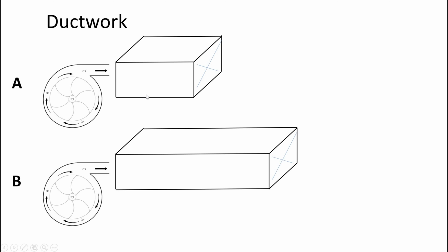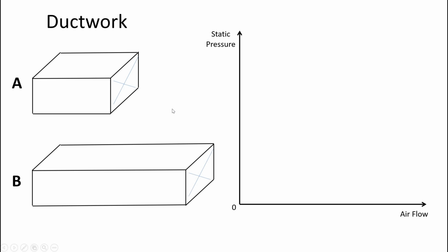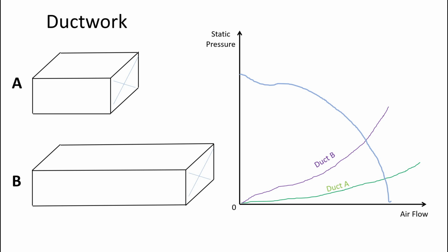The fan needs to create less static pressure to push air through ductwork A than through ductwork B. Let's illustrate it on the chart again. Low static ductwork A would look like this on the chart, and ductwork B would create higher static pressure for the fan, and on the chart it would look like this. Let's put our fan curve back. Now, with this simple example, let's see why it is so important to select the fan properly and set the static pressure properly. In this particular case, for ductwork A, small changes in airflow will cause significant changes in static pressure. This particular fan, set to this fan curve, will not run stable with ductwork A.